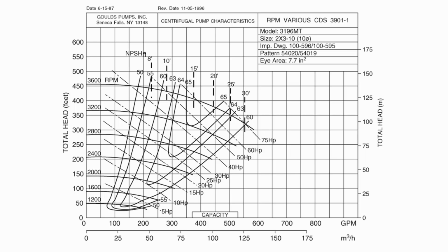Now the NPSH, that stands for the net positive suction head, and it's related to cavitation. And it tells you how close you are to the vapor pressure situation where the water is actually starting to boil inside the pump itself due to cavitation. We're going to talk about that next.